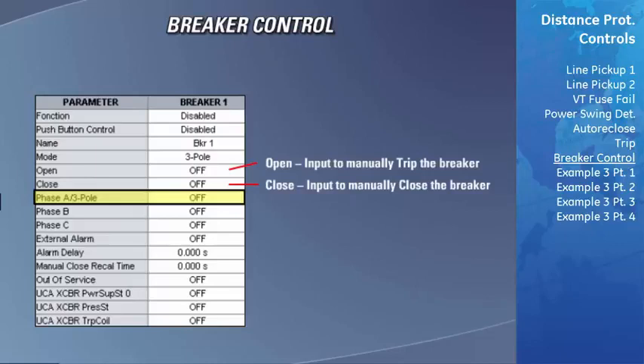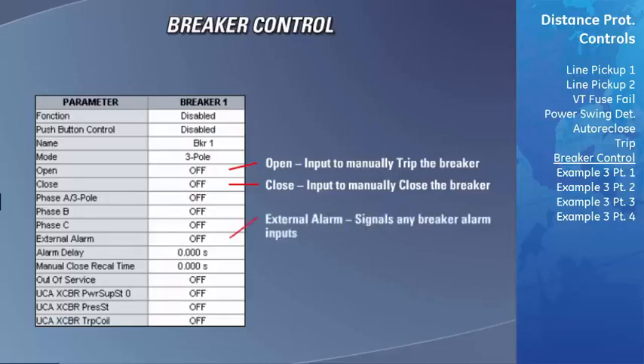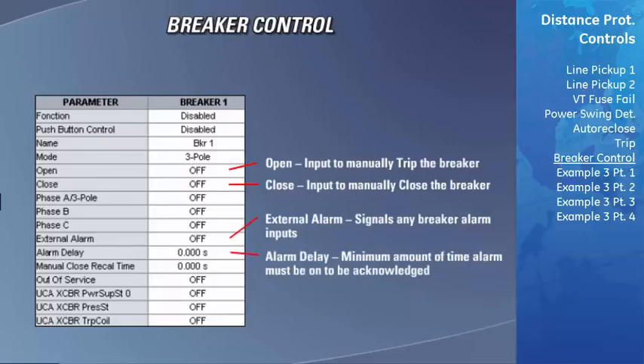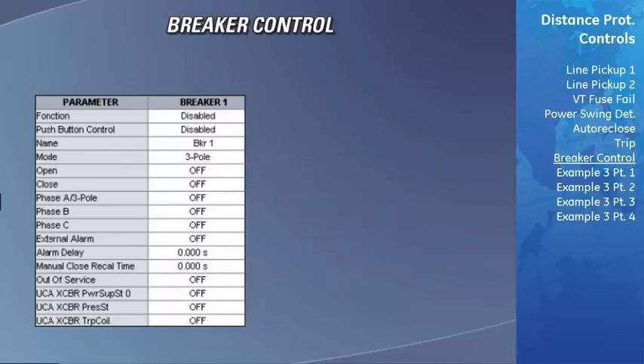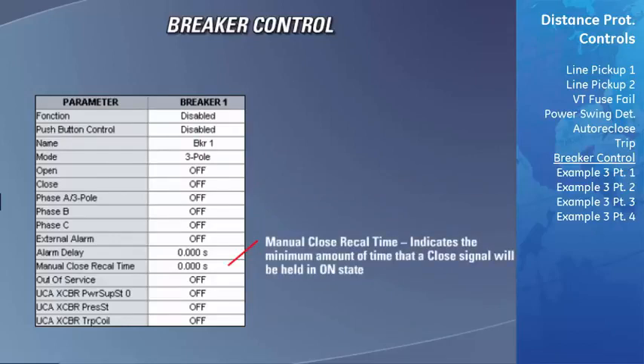In this field, select the contact input that is wired to the breaker 52A auxiliary contact. If single-phase tripping is being used, the status of each phase of the breaker needs to be indicated in the corresponding fields. The external alarm field lets the breaker know if any alarms, such as a low-pressure gauge, have been detected. This field will normally be a contact input wired to the alarm signal. The alarm delay field indicates the length of time the alarm must be on before it will be acknowledged by the breaker control feature. The manual close recall time specifies the minimum amount of time that the close signal will be held on to be sure that the breaker has enough time to close.